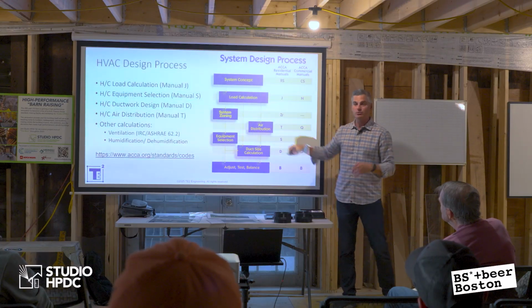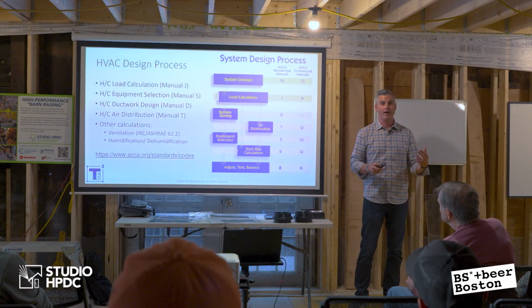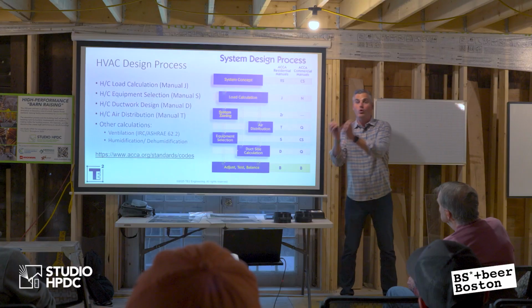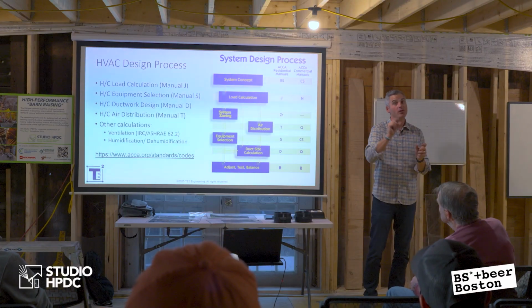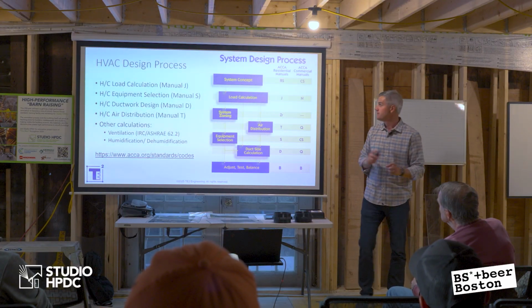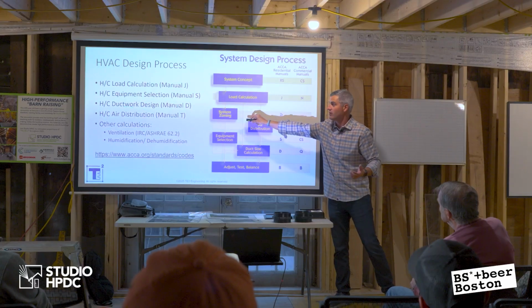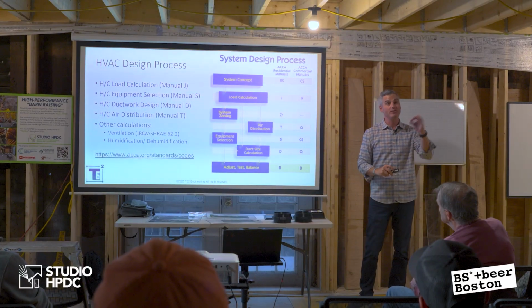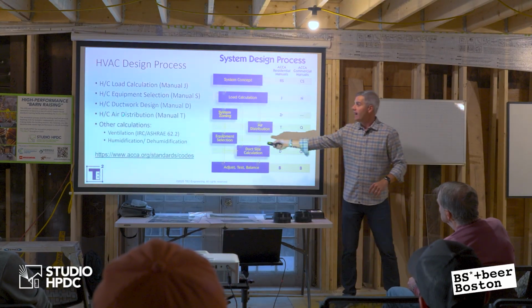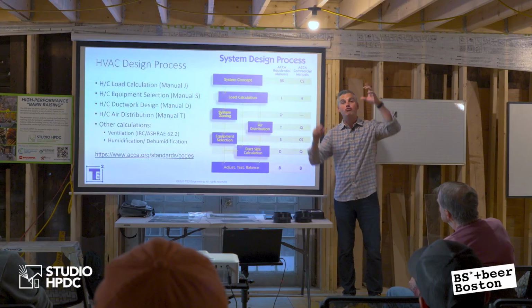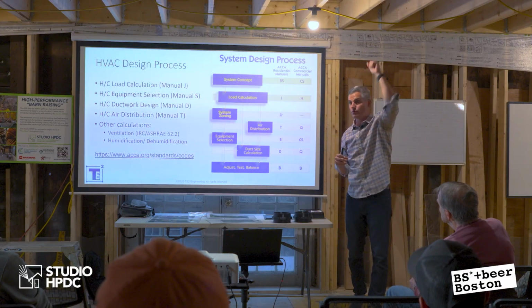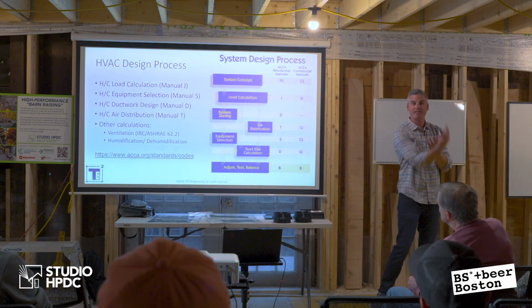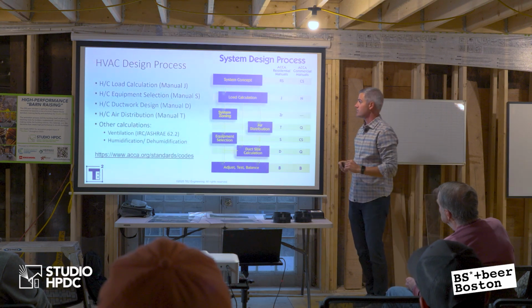Then there's Manual S, which is the equipment selection, right? If I have a load, I need to pick equipment to meet that load, and it's going to have to be a little bit bigger than that load in many cases. Then if it's got ductwork, I have to do a ductwork design. That's Manual D for ductwork, right? And then I have air distribution, Manual T. That's the registers, the air that blows out through the supply, and the register on the return that brings it in. That's Manual T, okay?